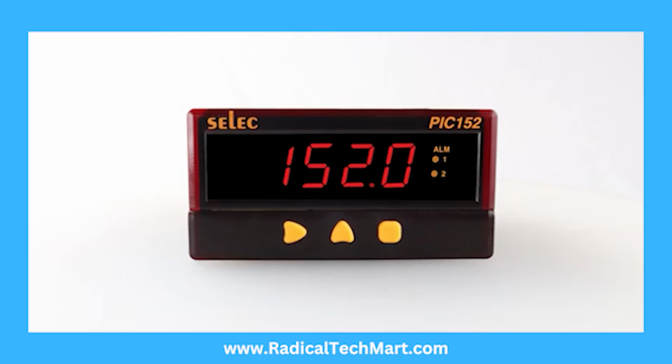The process indicator is used to indicate various process parameters such as temperature, pressure, flow, humidity, rate, etc. It comes with a 4-digit 7-segment LED display, which indicates the process value. It is provided with 2 LED indications for indicating alarm status, and we can also take retransmission analog output. 3 keys are provided for configuration purposes. With universal input, such as thermocouple, RTD, and analog input, it is feasible to use for multiple applications. It can be operated remotely as it is provided with RS485 Modbus communication.